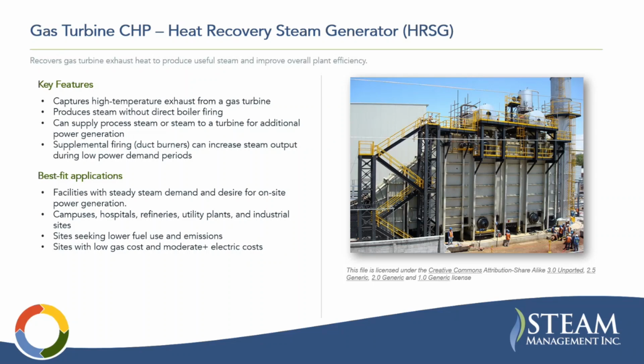These are basically, if you look at this transition duct here, this is the exhaust of a gas turbine, and that exhaust comes out hot enough to generate decent pressure steam. And then this is all heat exchange area as that flows across the boiler and then eventually up the stack. But so you're generating power with the gas turbine, and then you're generating steam with the heat recovery steam generator, which people call HRSGs for short.